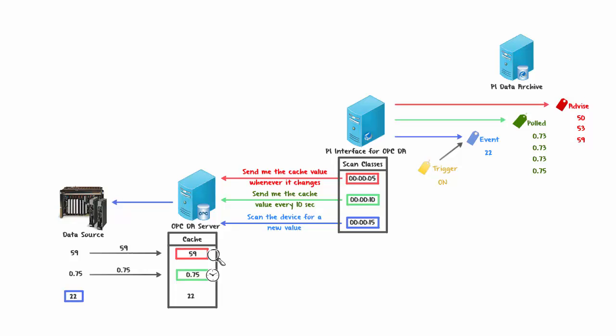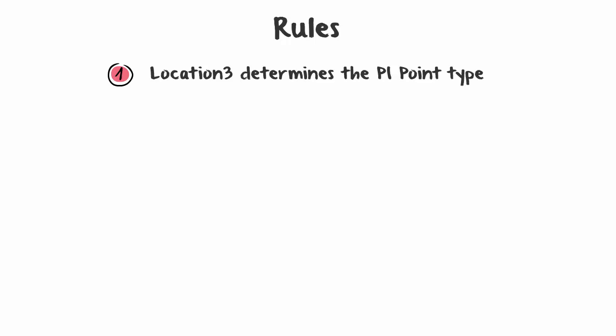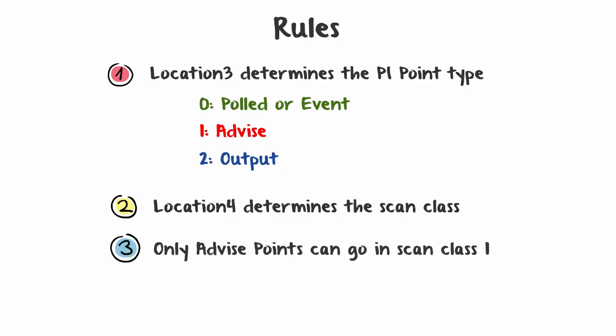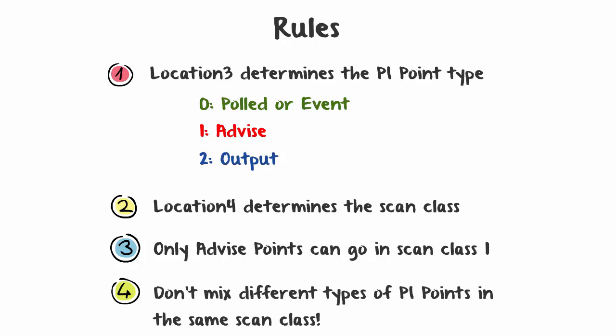Now let's look at some configuration rules. The Location 3 parameter of your PI Point determines the PI Point type: a value of 0 means a Polled or Event Point, 1 means an Advise Point, and 2 means an Output Point. Location 4 determines the Scan Class of your PI Point. Only Advise Points can go into Scan Class 1, as it's reserved for Advise Points. Finally, never mix different types of PI Points in the same Scan Class — for example, don't mix Polled and Advise Points — because these Scan Classes are OPC Server groups and the PI Interface won't know what kind of request to make.